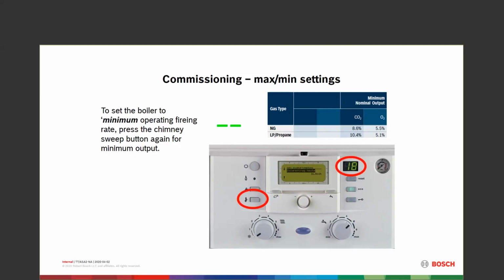Our book calls for us to do high fire first, low fire second. Really doesn't make any difference, other than my preference is low fire first because I have a lower firing rate. I can spend a little more time in it before the boiler goes to limit, before the system warms up too much. If you've got a big system, you're in the middle of the winter time, doesn't really matter at all. But if you're trying to set these up in the fall or in the summertime, it can certainly make a big difference. If you fire this on high fire at 140,000 or 150,000 BTUs, you're going to come up pretty quickly and not be able to get rid of that heat. So for me, I set them up in low fire and take it from there and move into high fire from there.